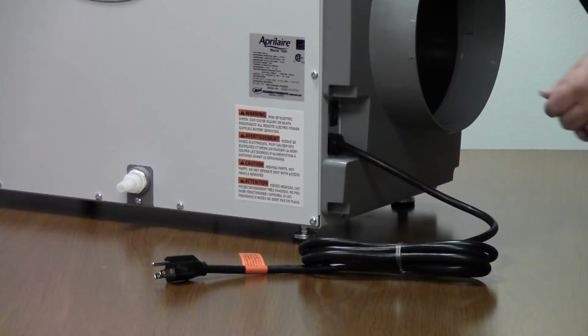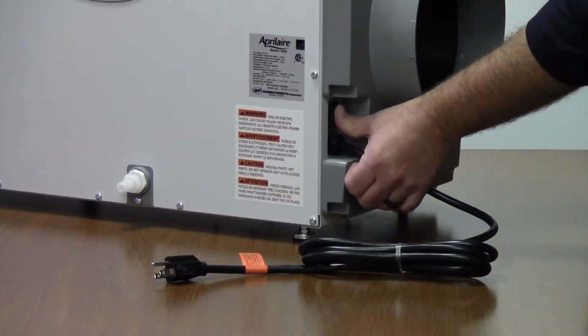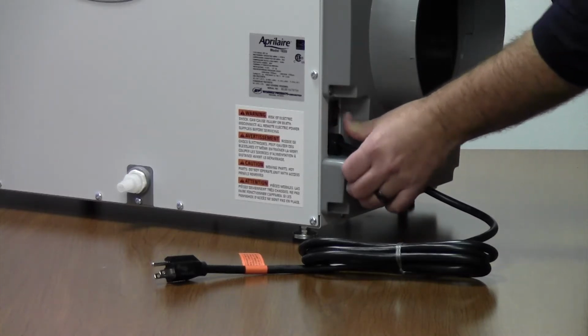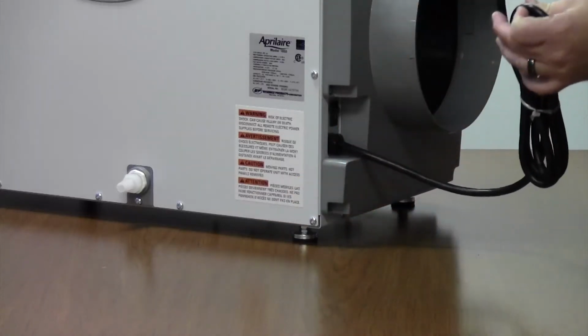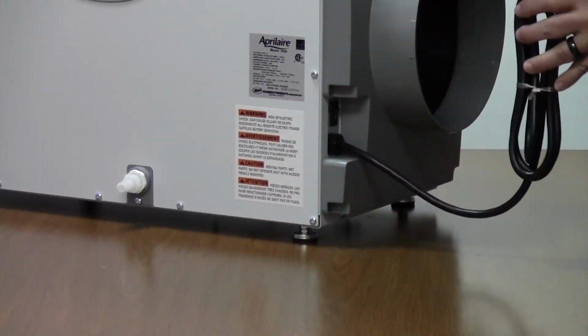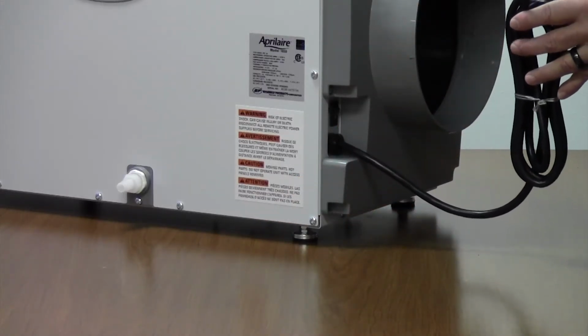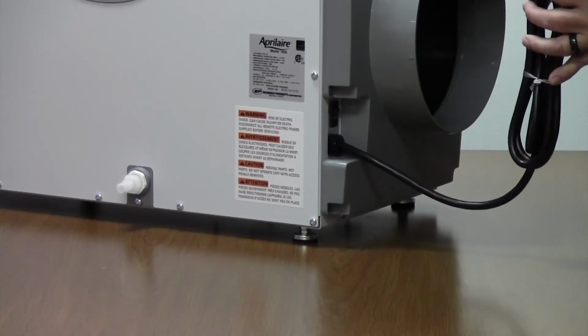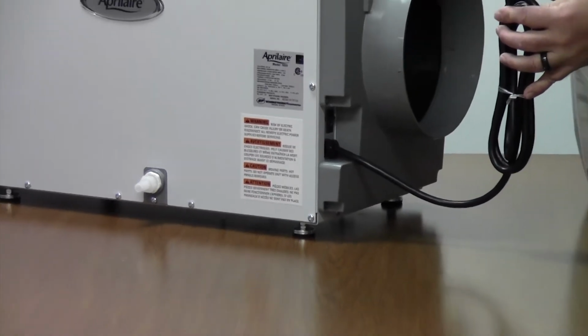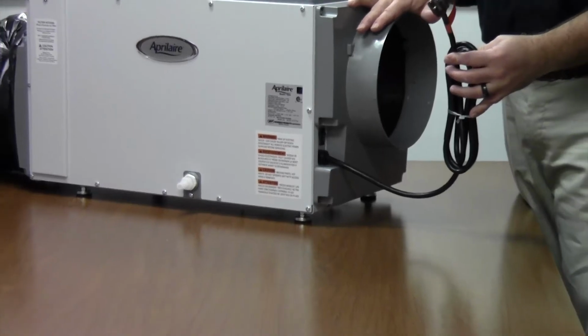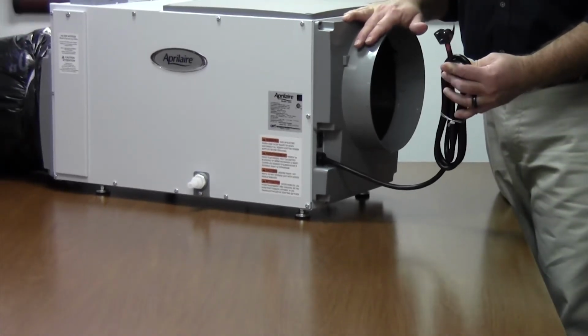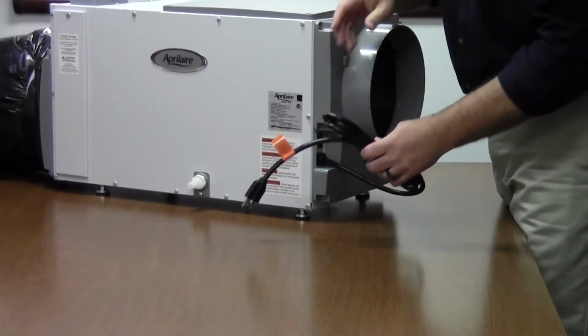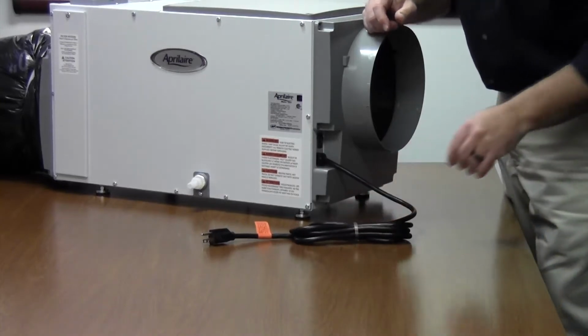Now for electrical connections, we have a little on-off rocker switch here, and the cord plugs into a standard 15 amp outlet. This unit draws 6.3 amps, so we don't require a dedicated circuit, just a lightly loaded 15 amp circuit with no other appliances on it. You should check with local codes to make sure that there's nothing else that they require.